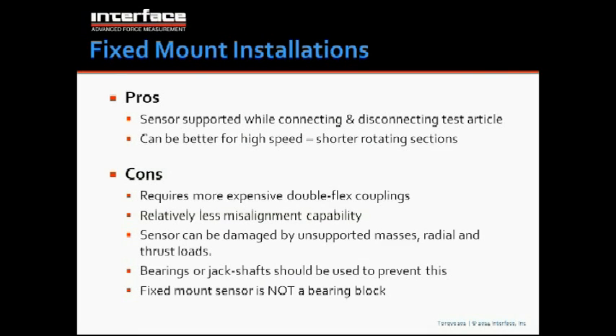Pros of fixed mount: the sensor's supported while you're connecting and disconnecting test articles. It can be better for high speed because it has a shorter rotating length. The cons would be that it requires a little more expensive couplings, relatively less misalignment capability, and the sensor can be damaged by unsupported masses, radial and thrust loads, and that's important. We want to avoid damage to the sensor if at all possible.